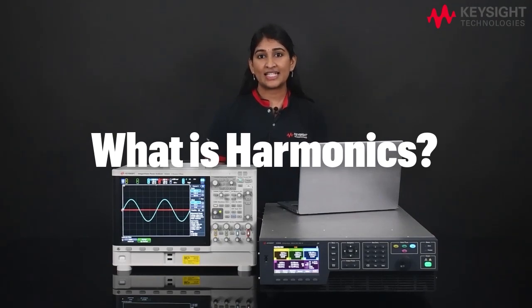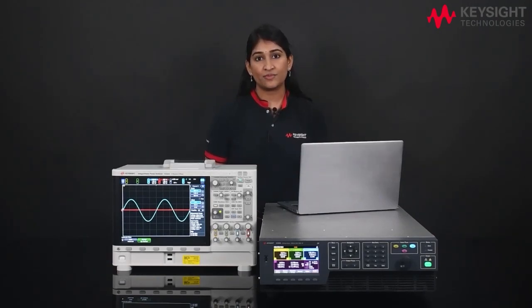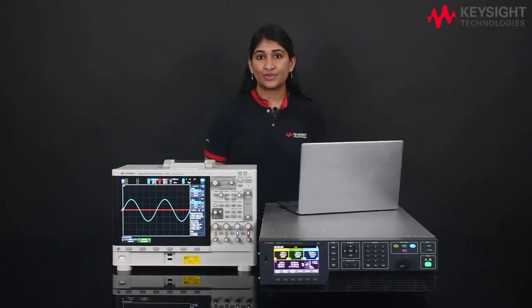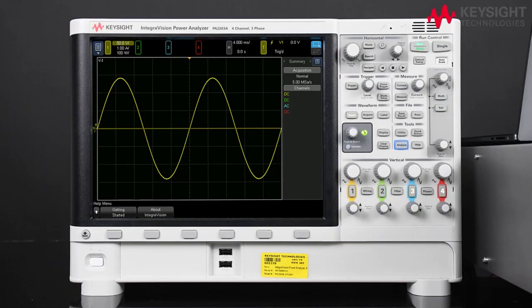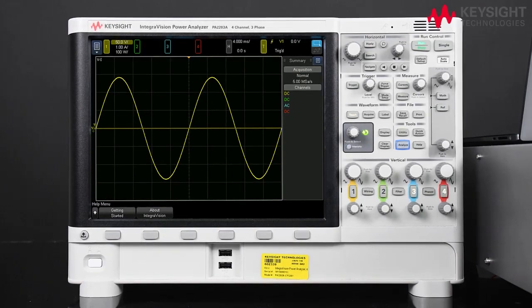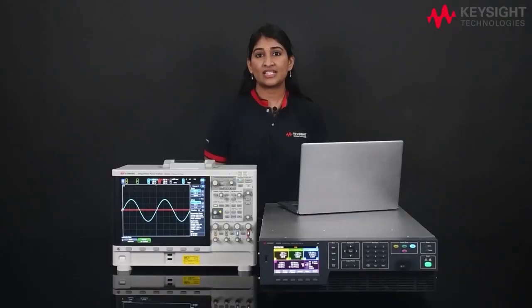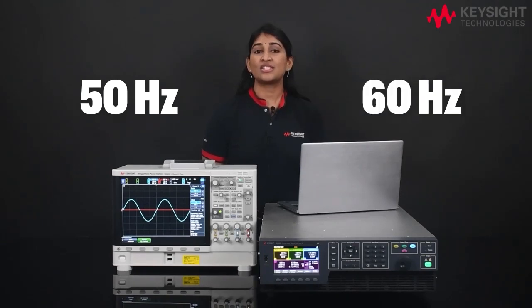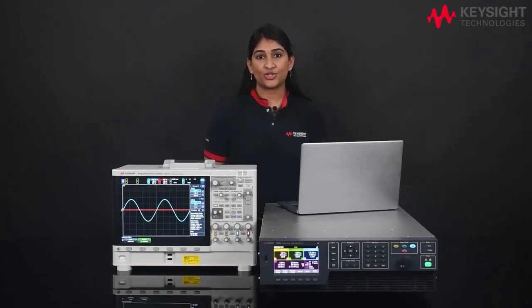Now, what is harmonics, you may ask? Harmonics are higher frequency waveforms superimposed onto the fundamental frequency. In other words, harmonics in our electrical power distribution system combines with the fundamental frequency of either 50 or 60 Hz to produce voltage waveform distortion.